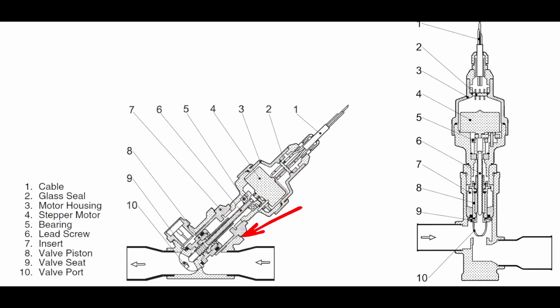Right here at this seam, this is where they thread into one another, and it is just a threading with a mechanical seal typically. Some of them will have a Teflon seal in here, but a lot of them that I've seen, it's usually a mechanical seal, meaning that we're taking brass to brass and making a seal that way. And this is a machined surface, so the friction of the two joining here, that's where you have to get your torque really well, will make this seal.